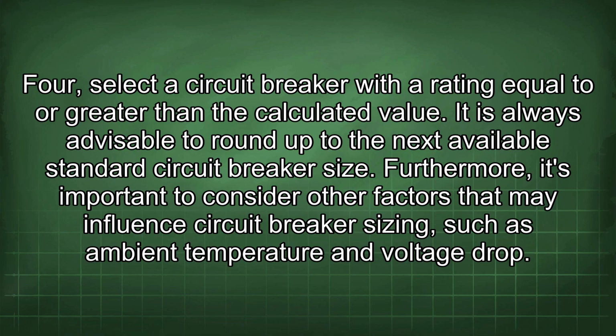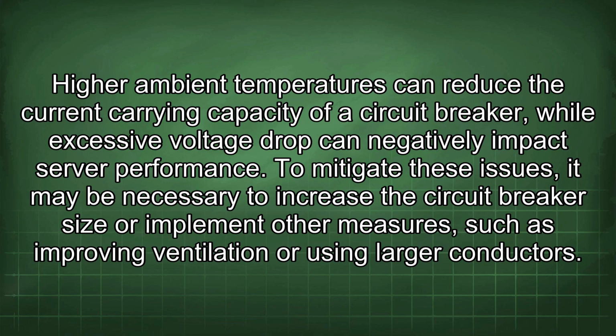Furthermore, it's important to consider other factors that may influence circuit breaker sizing, such as ambient temperature and voltage drop. Higher ambient temperatures can reduce the current carrying capacity of a circuit breaker, while excessive voltage drop can negatively impact server performance. To mitigate these issues, it may be necessary to increase the circuit breaker size or implement other measures, such as improving ventilation or using larger conductors.